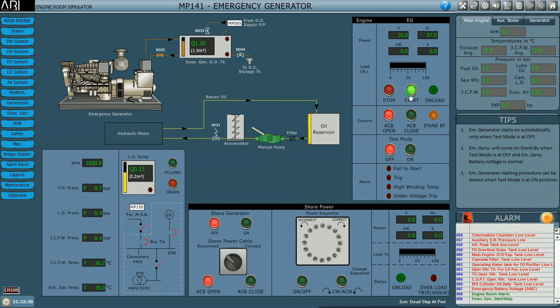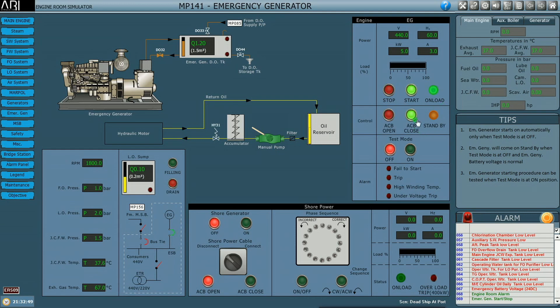You can see the engine has started — it is with the help of the battery which was kept charged. The voltage and frequency is developing. Once the voltage is developed up to 440 volts, the engine will come on load automatically; the ACB is going to close and the engine is on load now. This is what would happen in a blackout — the emergency generator will start and come on load within 45 seconds.